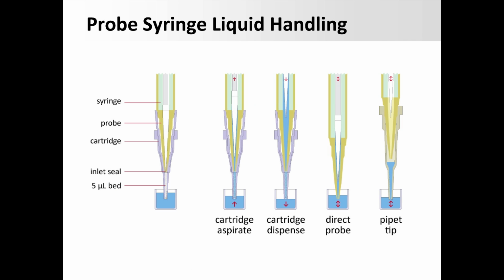Now, the probe syringe technology is a little different. Here we're using a syringe instead of centrifugal force to drive liquid through the bed. The syringe is designed with a special probe extension that gives us virtually zero dead volume, typically a microliter or less inside the syringe. So there can be no air bubbles of any substance trapped in the syringe, and washout and carryover is virtually eliminated.